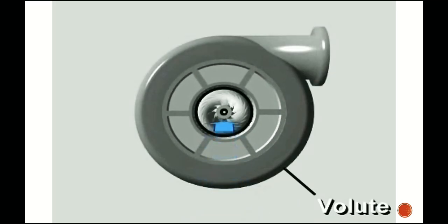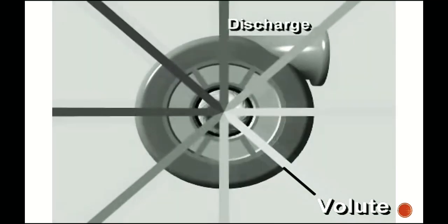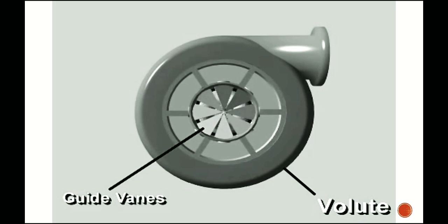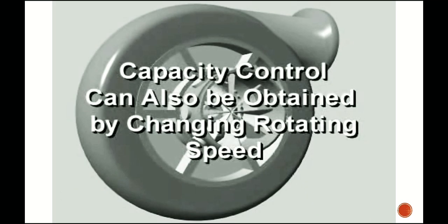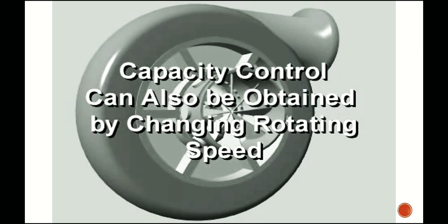The volute-shaped casing collects the slow-moving, high-pressure vapor from around the diffuser and conveys it to the discharge connection of the compressor. Inlet guide vanes control the centrifugal compressor's capacity. These movable vanes are located in the suction opening. With vanes fully open, the compressor produces its full cooling capacity. As the vanes are closed, they reduce refrigerant flow through the compressor, reducing the capacity of the refrigeration cycle. Capacity control can also be obtained by changing the rotating speed.